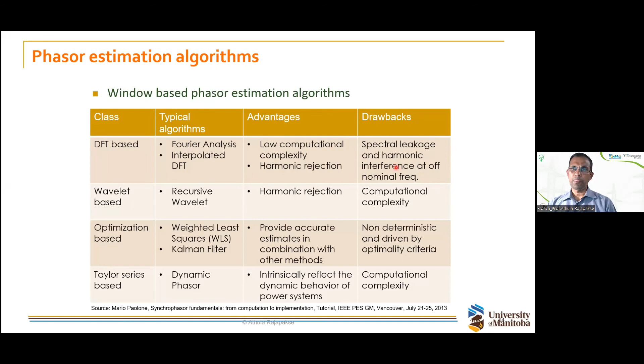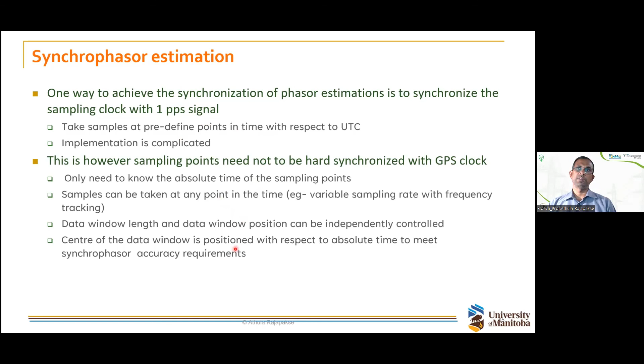What we've discussed so far is just phasor estimation. To make it a synchrophasor, you need to synchronize your reference sine and cosine function with the 1 PPS signal from the atomic or satellite clock. That means your reference cosine signal's zero phase angle should occur at the start of the new UTC second. With this signal, it's quite easy to do. You have to resynchronize at the beginning of every second, because otherwise your clocks will drift with time. Normally you don't hard-synchronize all sampling points with the satellite clock, but your time stamping needs to be properly done.